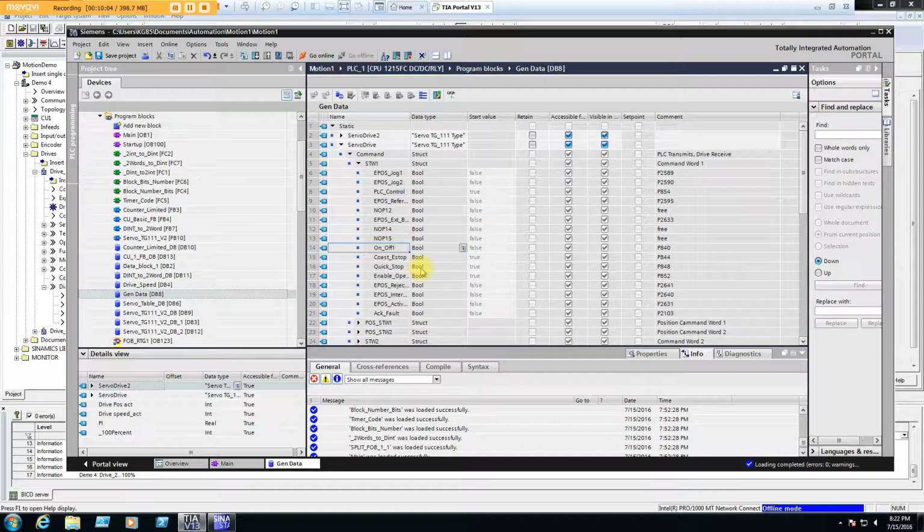Also, when you go into double words, it swaps around the words because the words come around the same way, you know, high word first, low word first. Got to make sure you get that right. Usually, the phone call I would get would be like, "Well, it looks like the communications is established, but all the data is garbage." And usually, without even looking at it, I'm like, "Okay, well, I know that you got the little Endian, big Endian transfer you got to do."